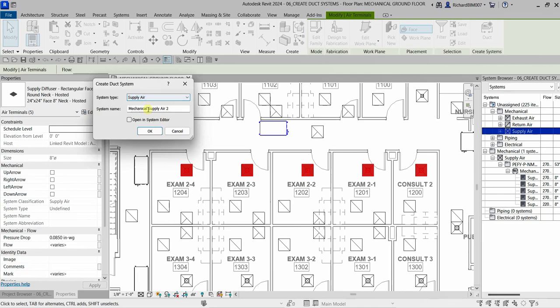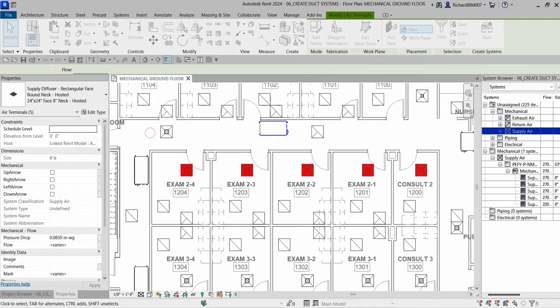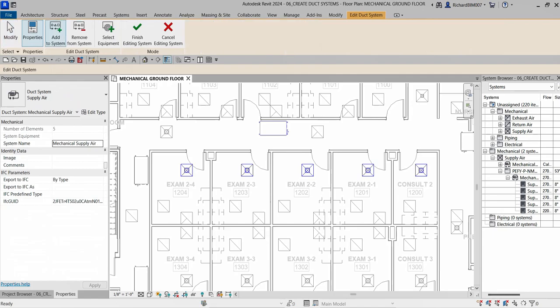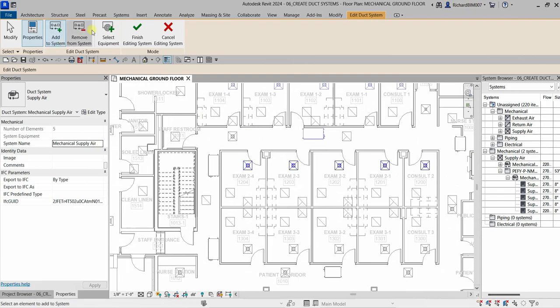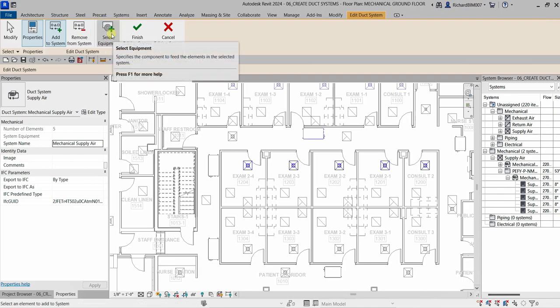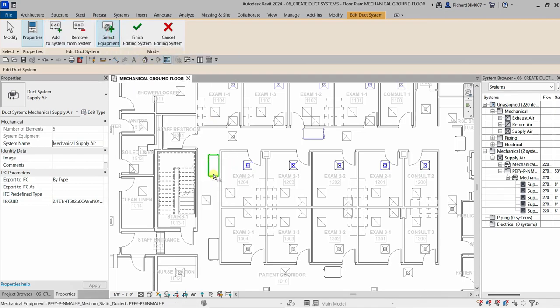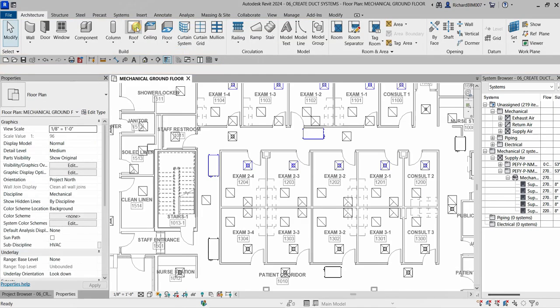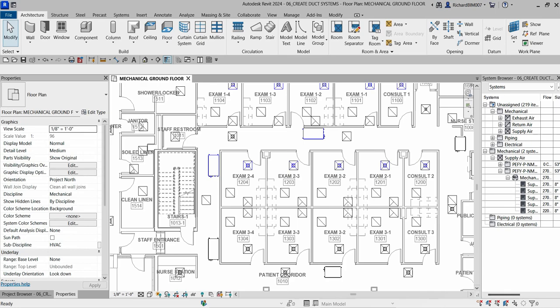With all air terminals selected, click 'Create Duct System'. The same dialog appears — system type, system name, and option to open the system editor. Click OK, then in the system editor click 'Select Equipment', choose the supplying mechanical equipment, click it, and then click 'Finish Editing System'. The system is now created.